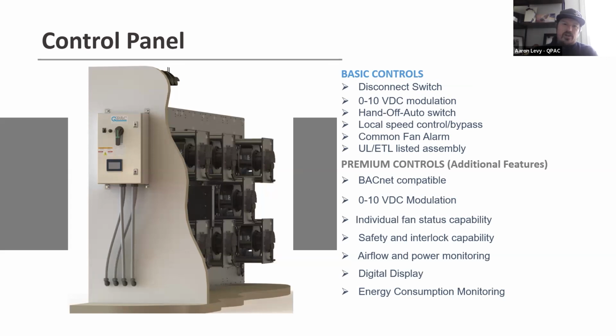It'll also allow you to run it at constant volume or constant pressure, depending on how the system is designed. We give you pressure transducers on a premium controller. There's a high side port into the quick connect box and a low side port on the fans, and that'll read out static pressure to the system.